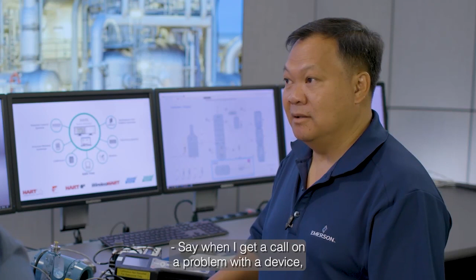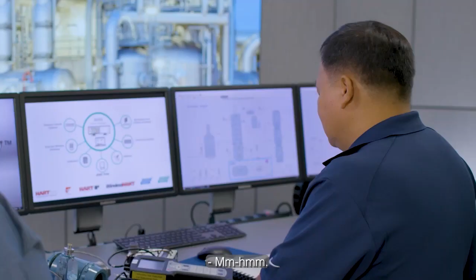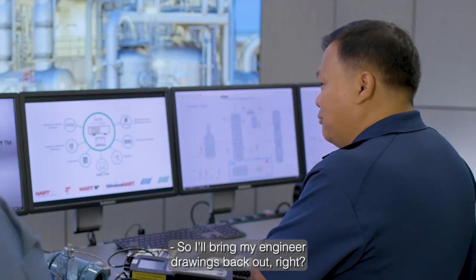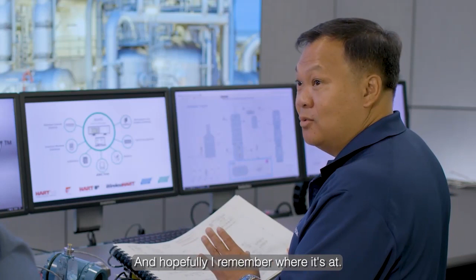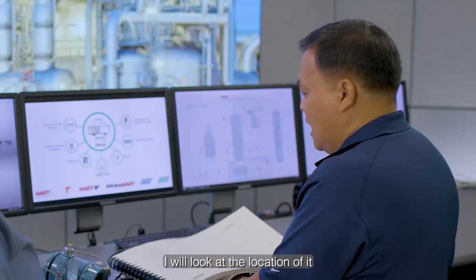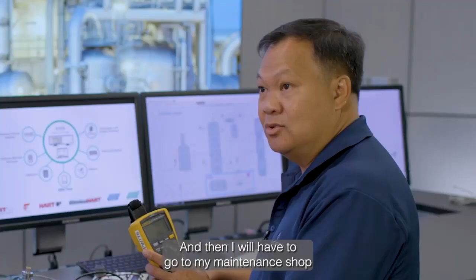When I get a call about a problem with a device, I need to find out where it's located. I bring my engineering drawings out, go through all the pages, and hopefully remember where it's at. Once I figure out where it is, I look at the location and understand what I need to bring out to the field. Then I go to my maintenance shop to check out and calibrate everything with the proper procedures, including the field communicators and the volt-ohm meters. These are the three main pieces of equipment I need to troubleshoot a device.